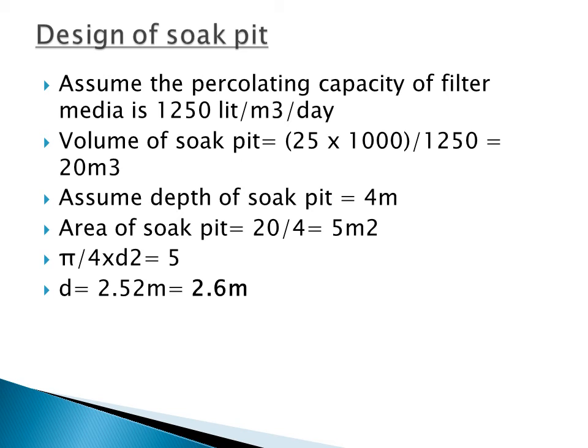The depth of the soak pit is assumed as 4 meters. Therefore, the area of the soak pit equals volume divided by depth: 20 divided by 4 gives 5 square meters. Since the cross-section is circular, using the area formula pi over 4 times D squared equals 5, the diameter D is obtained as approximately 2.52 meters, rounded off to 2.6 meters. The question also asks you to draw a rough sketch of the septic tank and soak pit with dimensions marked.